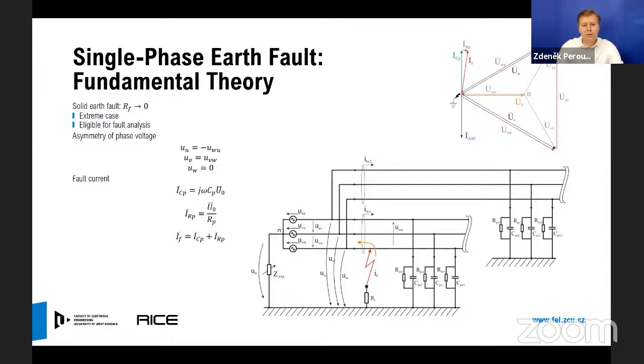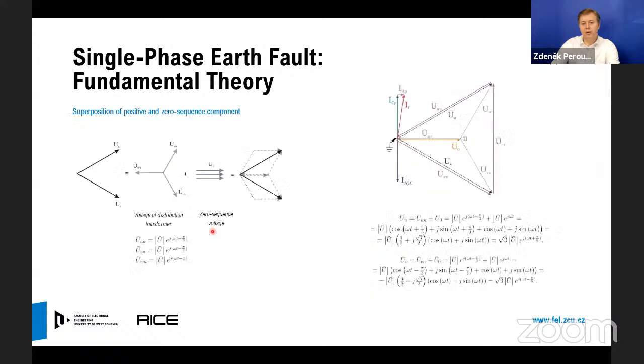I think all of you are very familiar with single phase earth fault theory. Just to remind you, if we operate insulated or high impedance grounded power distribution grids, the earth fault means that there exists a conductive path between one of the grid phases and the ground. The fault current flowing through the place of the fault has two components, a capacitive component and an active component. We are trying to mitigate the fault current in the system, to still be able to operate the grid under the earth fault.